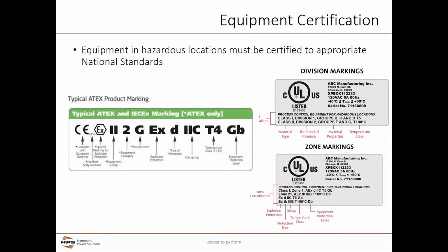UL is classified by divisions and classes, and the classes define the substances, and divisions define the operating conditions. Those classes are also split into subgroups to determine specific or equivalent substances. The ATEX or IECEx label will tell you exactly where the equipment can be used based on the equipment classifications and zones specified. All of the numbers and letters on the label correspond to the level of protection offered and in which environment the equipment can be used.